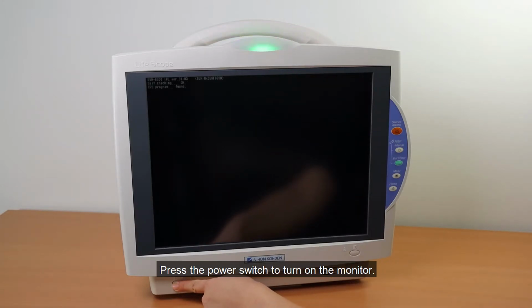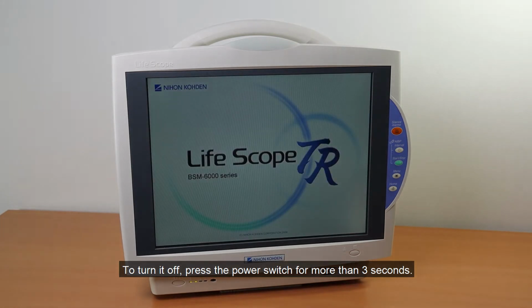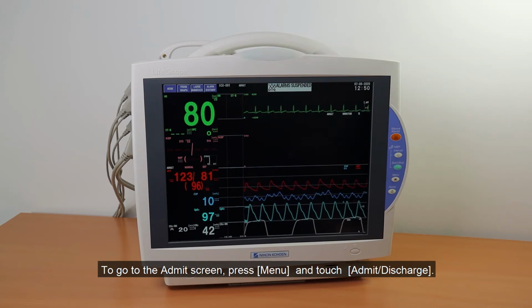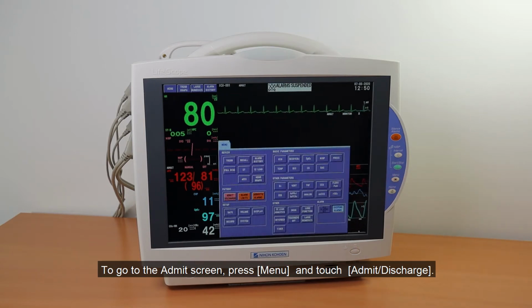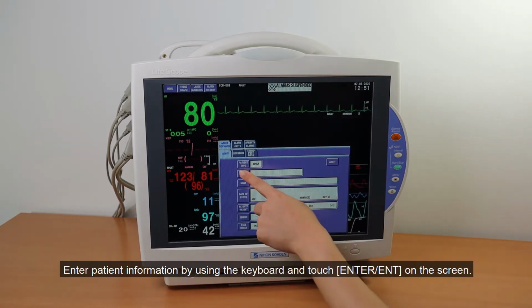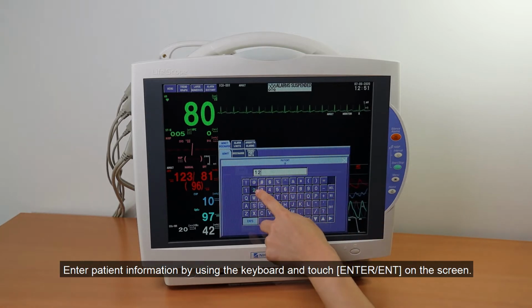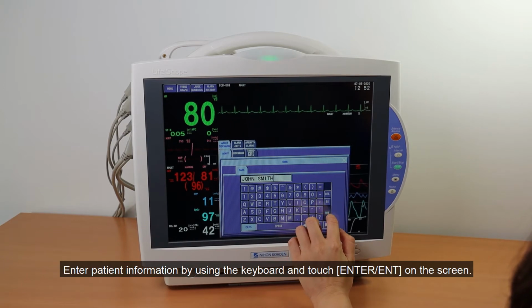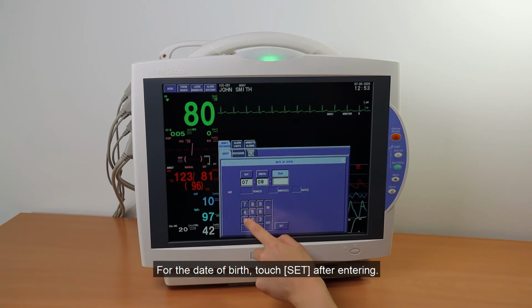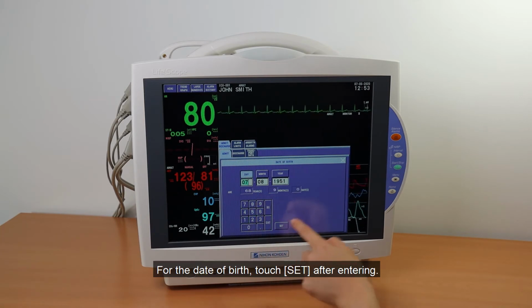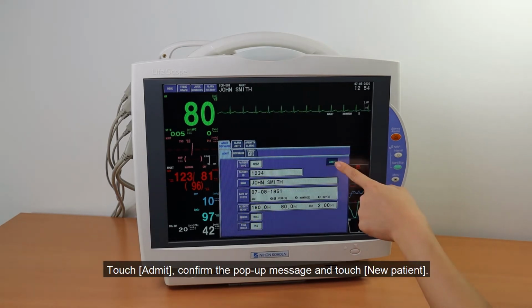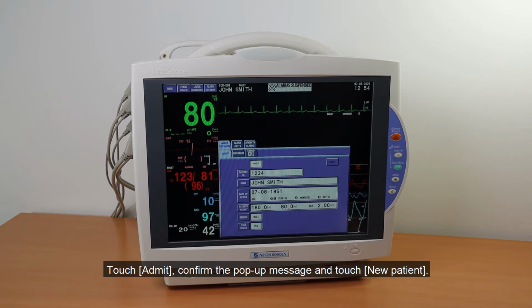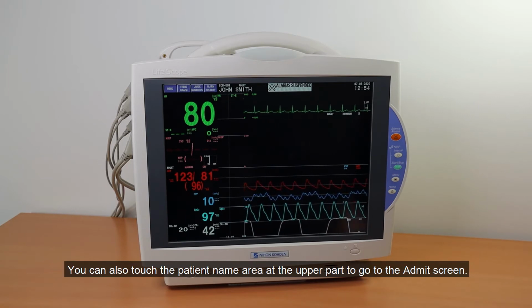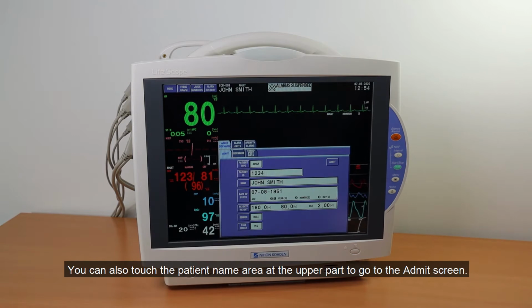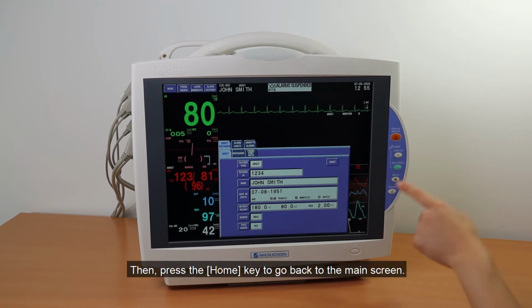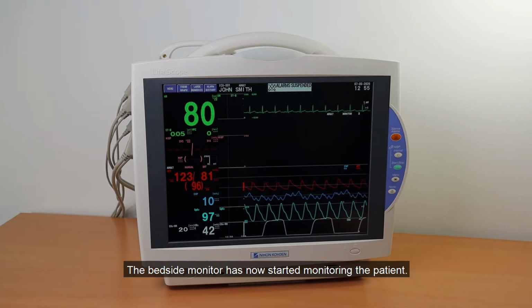Press the power switch to turn on the monitor. To turn it off, press the power switch for more than 3 seconds. To go to the Admit screen, press Menu and touch Admit Discharge. Enter patient information by using the keyboard and touch Enter. For the date of birth, touch Set after entering. Touch Admit, confirm the pop-up message, and touch New Patient. You can also touch the patient name area at the upper part to go to the Admit screen. Then, press the Home key to go back to the main screen.